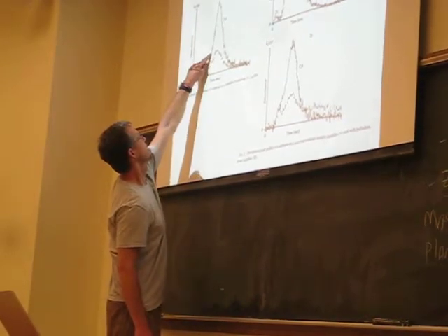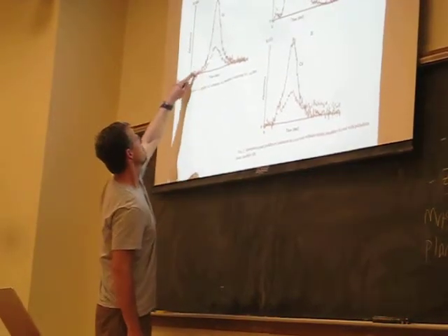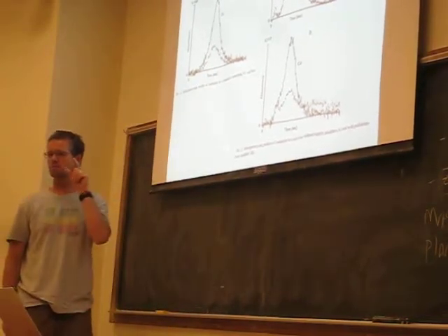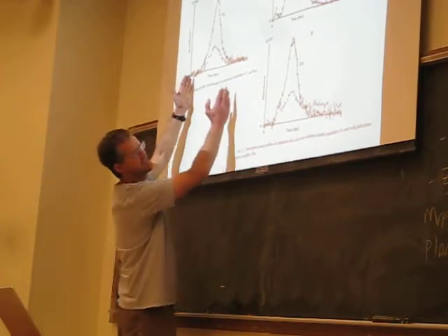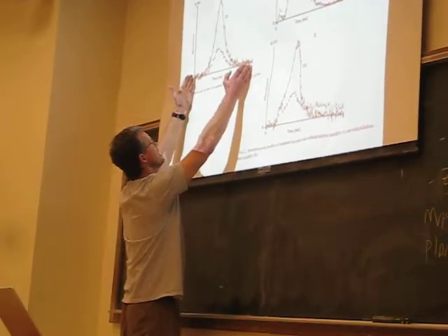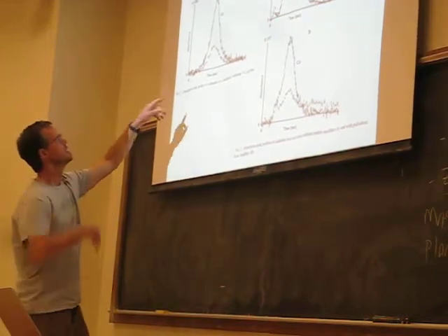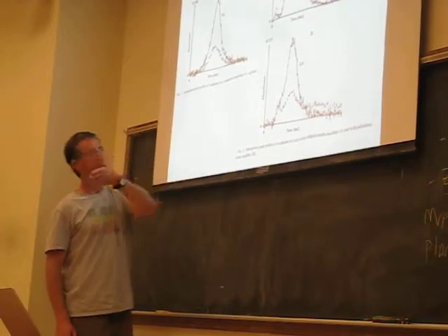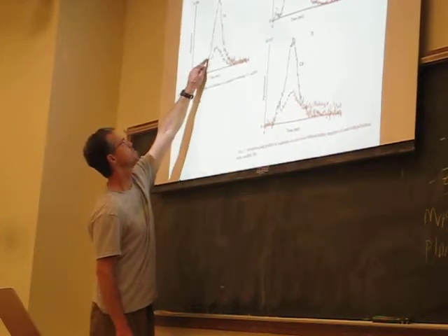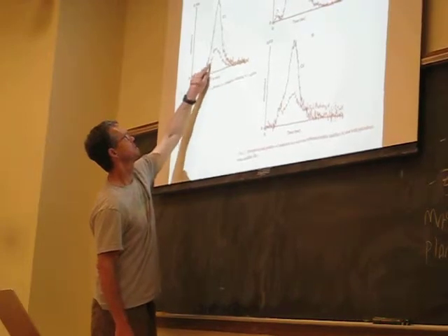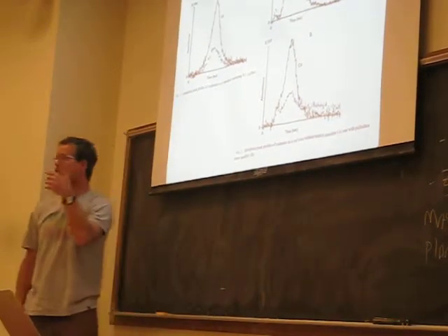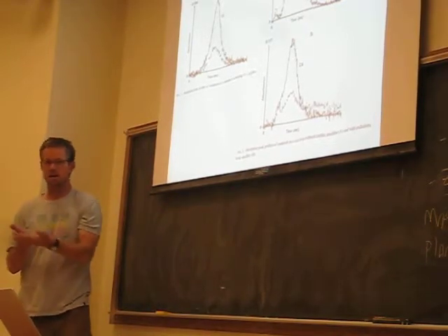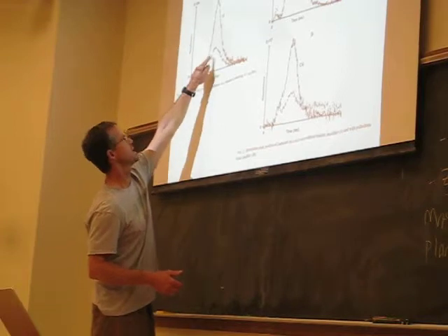They show the two lines. One is the analyte, cadmium, which is the atomic absorbance, and one is the background non-atomic absorption spectrum, shown over the 5 seconds that they were taking the reading during the volatilization stage. This is just a standard with just acid and cadmium in it, like you guys would generate. You see a relatively high analyte peak and a relatively low background peak that coincides with it. The instrument is able to correct for that because it has Zeeman background correction cycling between on and off, measuring the total signal versus just the background.